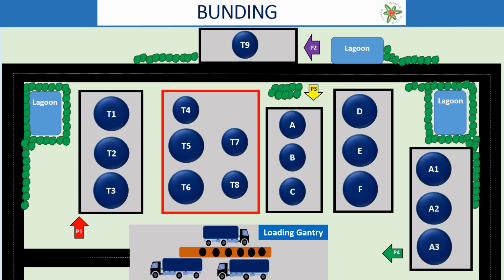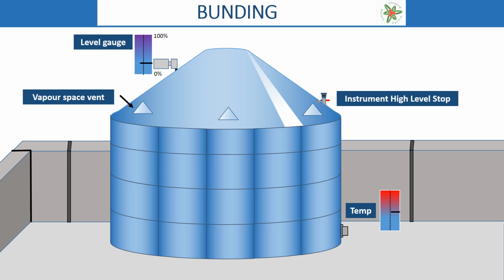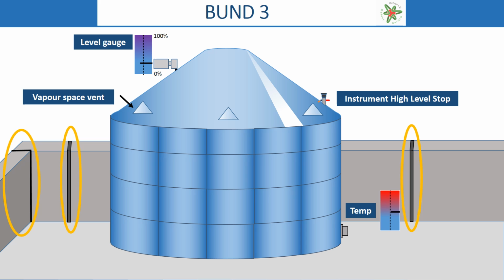Bund 3 contains tanks T4, T5, T6, T7 and T8. It's owned by the Northern Company, that's us. The bunds are constructed with concrete, and the joints are sealed, as well as sealing where any pipes pass through the bund walls.